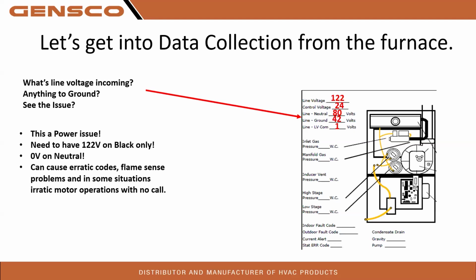So we have some issues that are going to happen, right? We shouldn't have anything on neutral. We're going to have erratic codes, flame sense problems. In some situations, especially in the old 40s, since white is unchecked power, we could have some erratic motor operation, like an inducer motor turning on for no reason, or a blower motor tapping on. So just with this little bit of information, we've already found a problem, right?